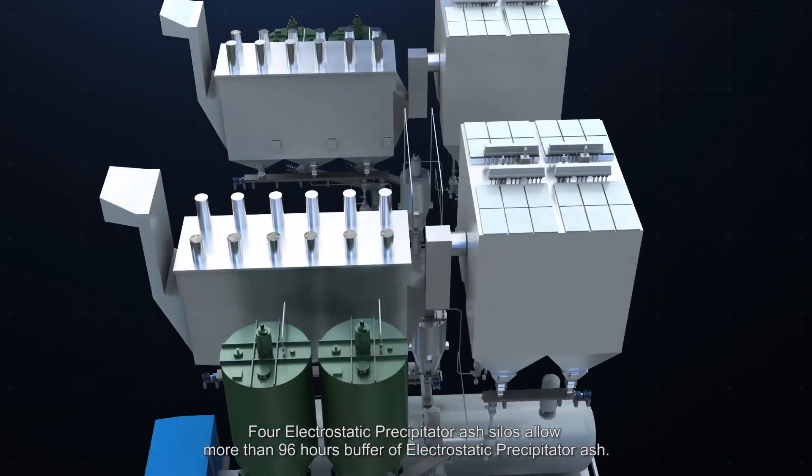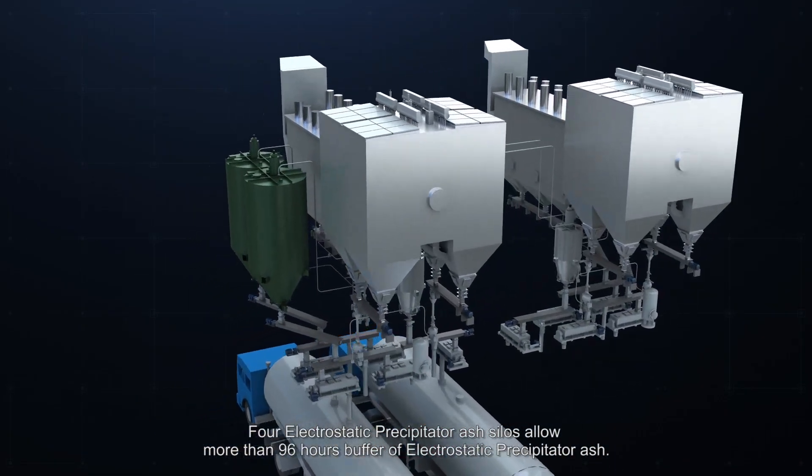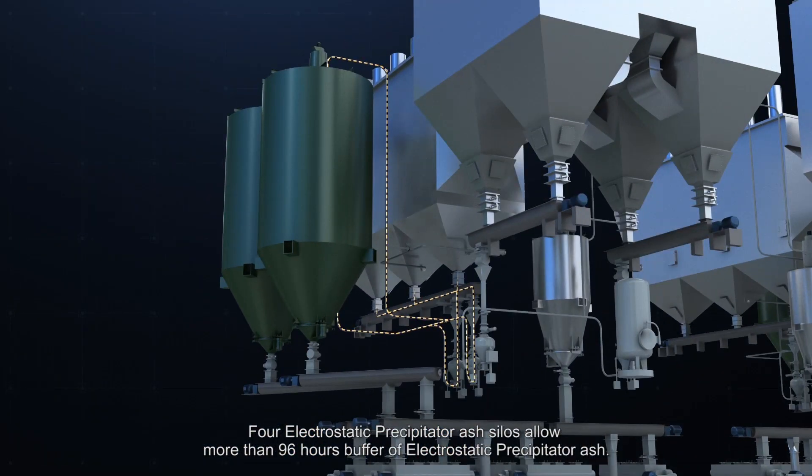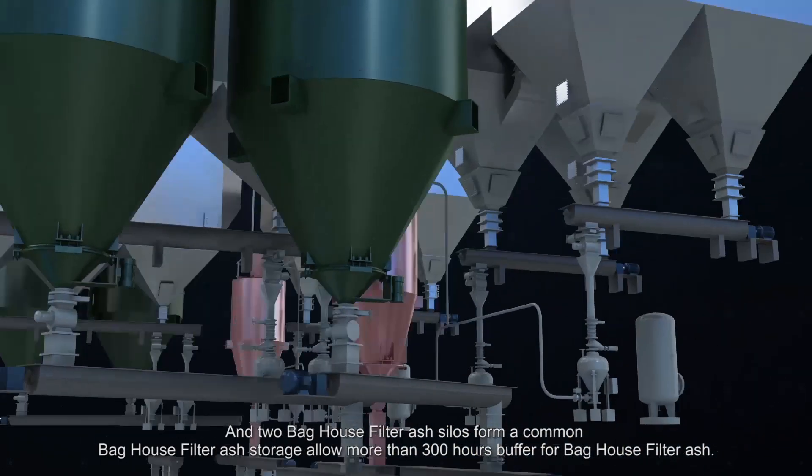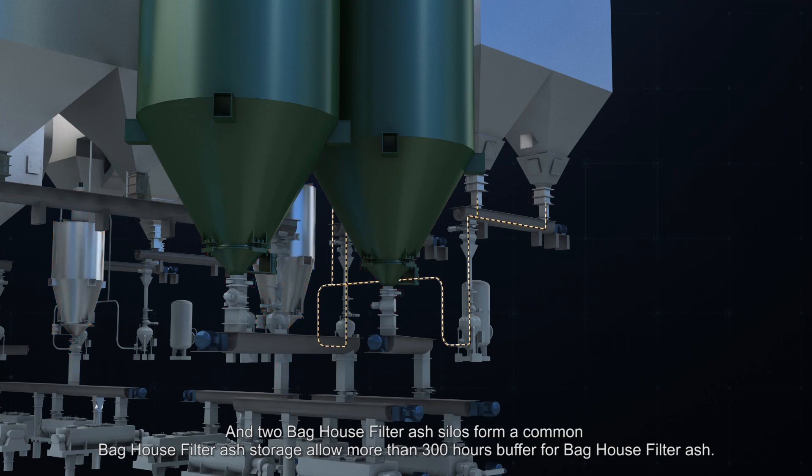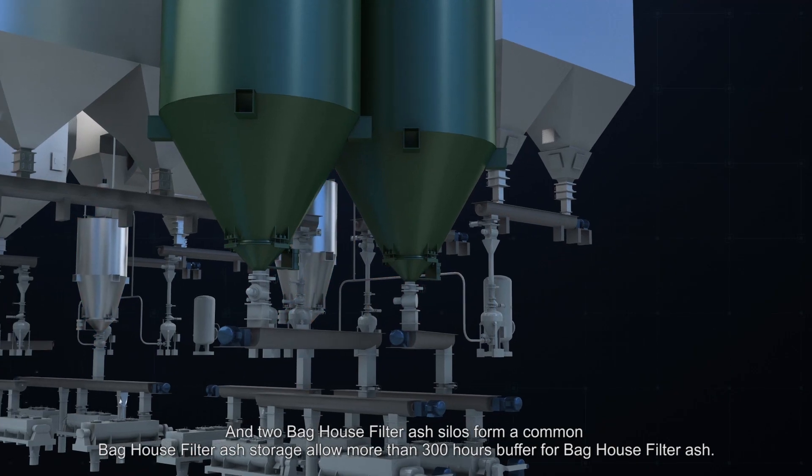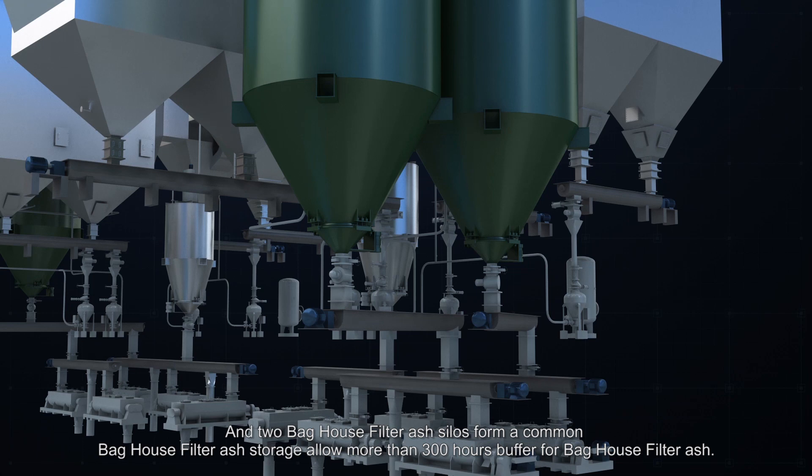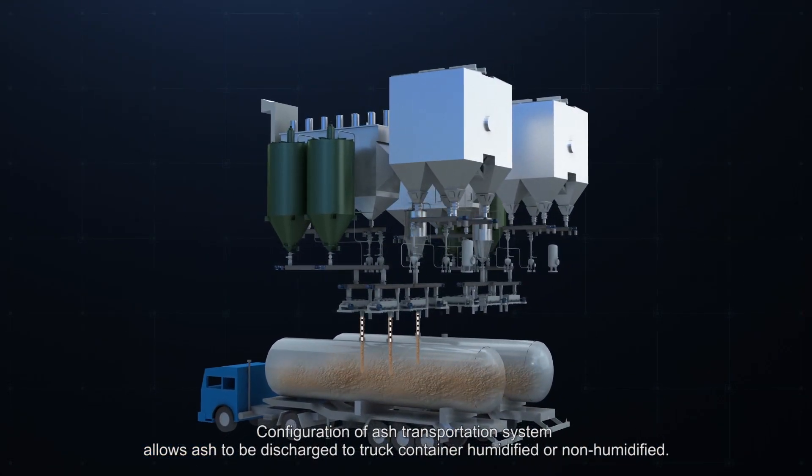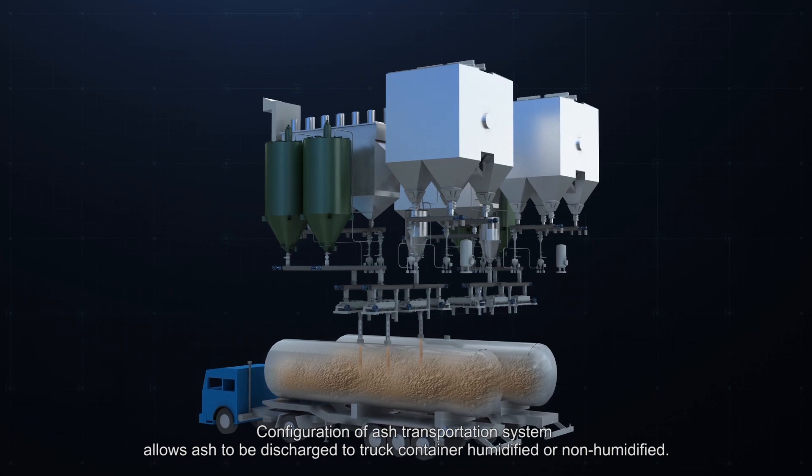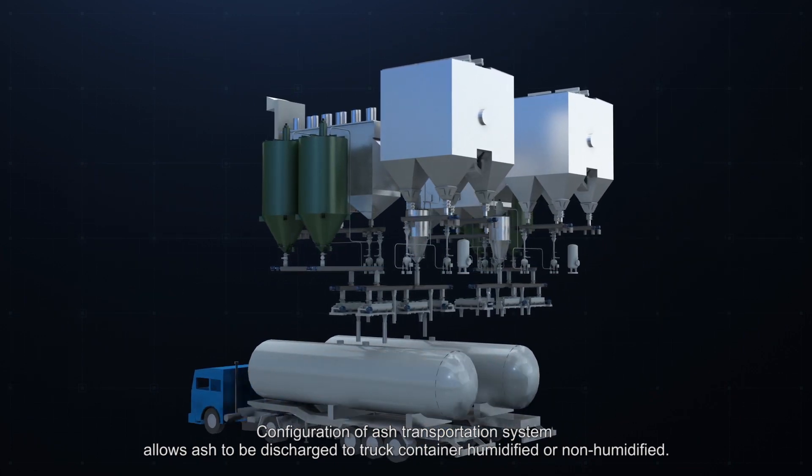Four electrostatic precipitator ash silos allow more than 96 hours buffer of electrostatic precipitator ash. And two bag-house filter ash silos form a common bag-house filter ash storage allow more than 300 hours buffer for bag-house filter ash. Configuration of ash transportation system allows ash to be discharged to truck container humidified or non-humidified.